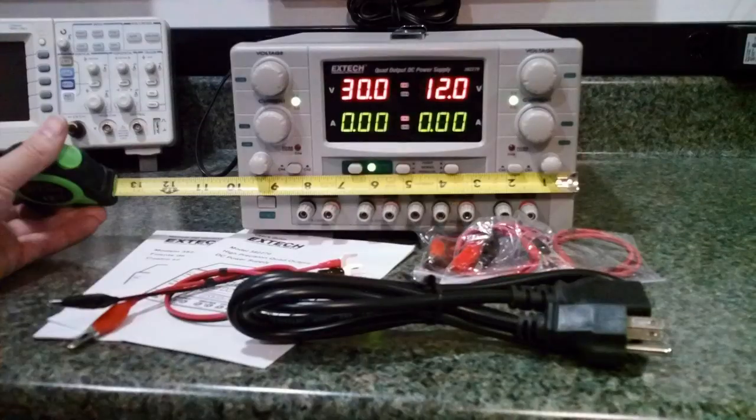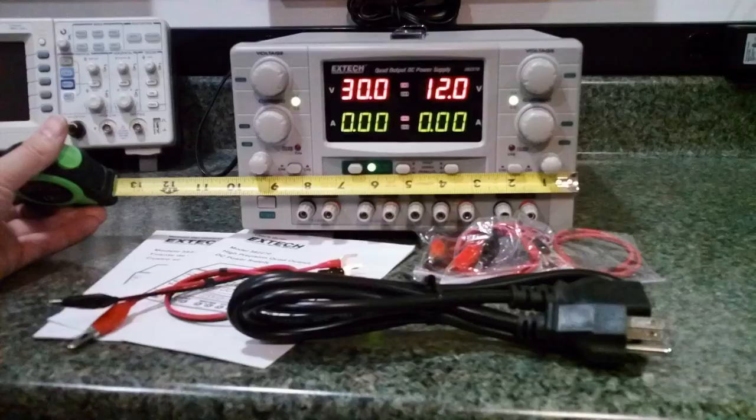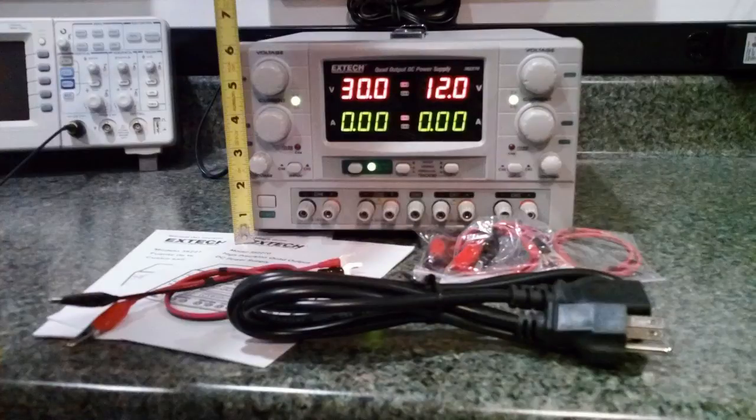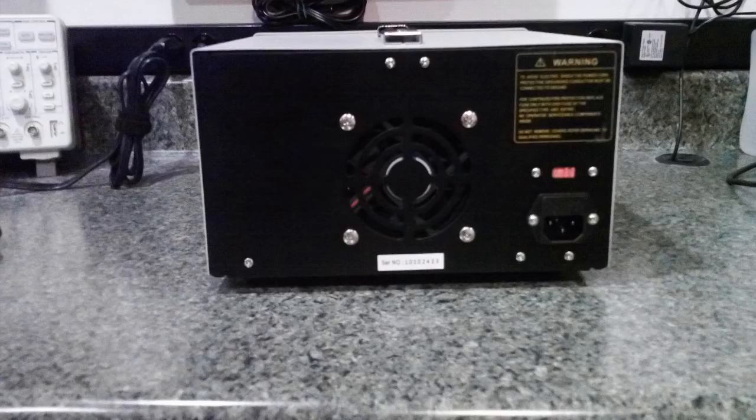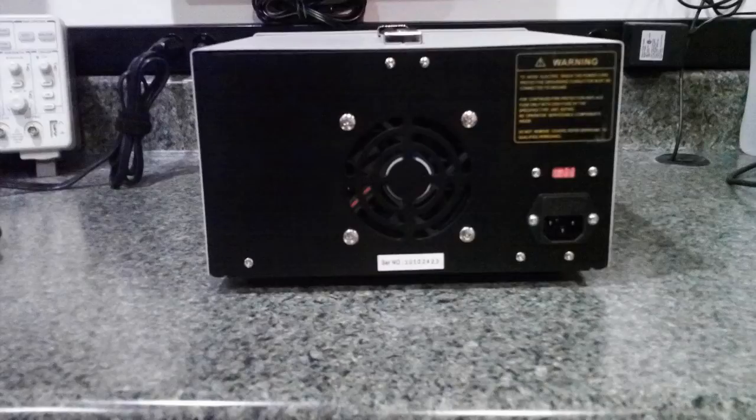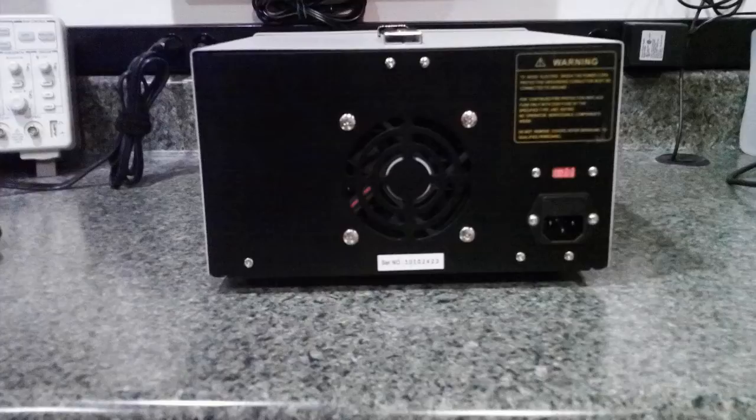The dimensions of the power supply are 10 inches wide, about 6 inches high, and a little over 11 inches deep. It does have a fan on the back that requires a few extra inches of clearance for cooling, and the right and left have vent holes, which require at least an inch for cooling.